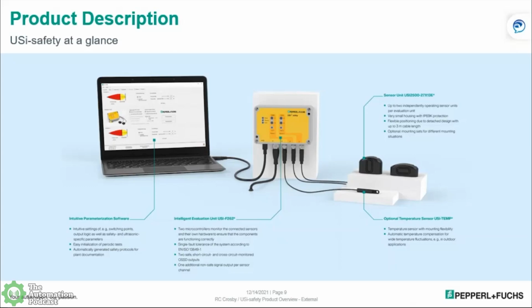Starting with the evaluation unit, it's the yellow box in the middle of the screen, which I just held up a few seconds ago. Within it, you have the two microcontrollers per channel to give you that redundancy, to give you that single fault tolerance according to EN ISO 13849, category 3 PLd. Each channel has two safe OSSD outputs, as well as a non-safe signal output for your warning zone. So you can set up a protected zone and a warning zone.